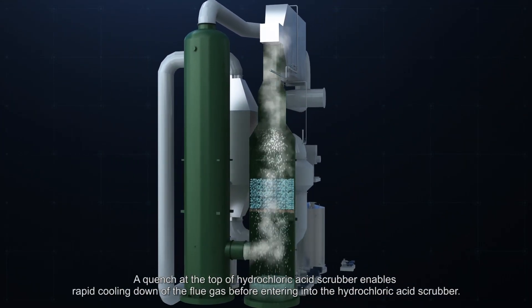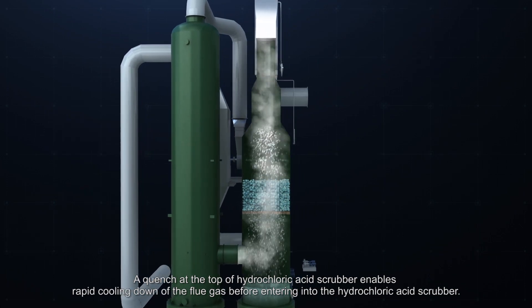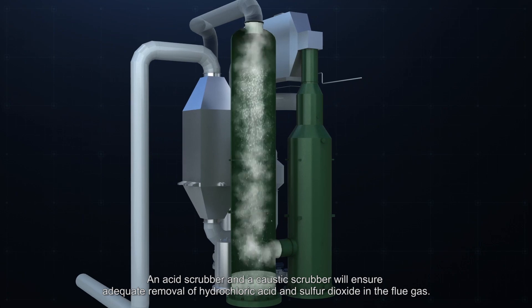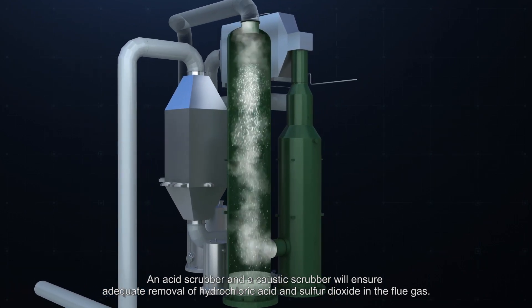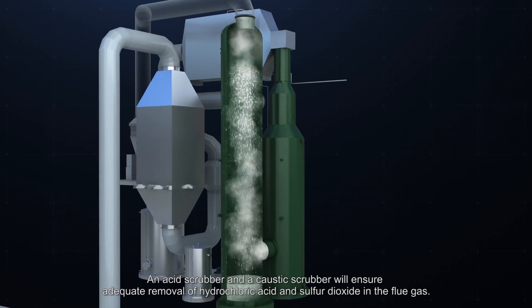A quench at the top of hydrochloric acid scrubber enables rapid cooling down of the flue gas before entering into the hydrochloric acid scrubber. An acid scrubber and a caustic scrubber will ensure adequate removal of hydrochloric acid and sulfur dioxide in the flue gas.